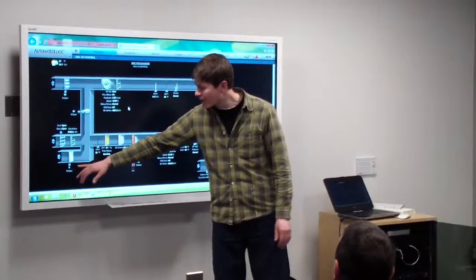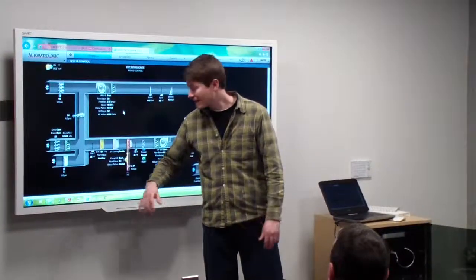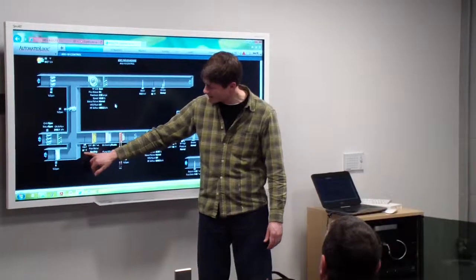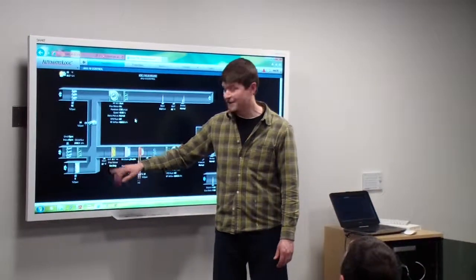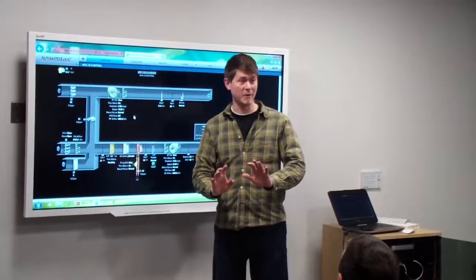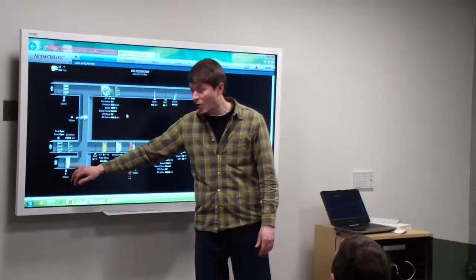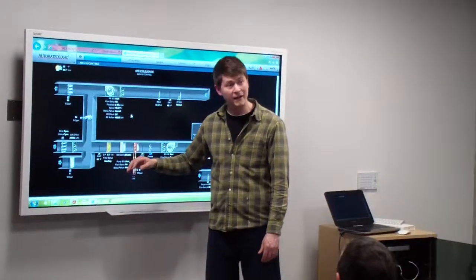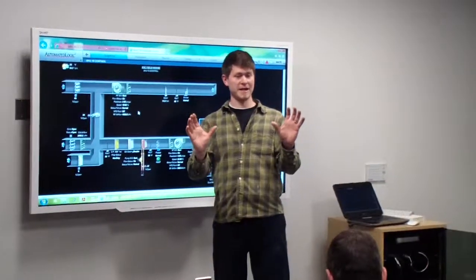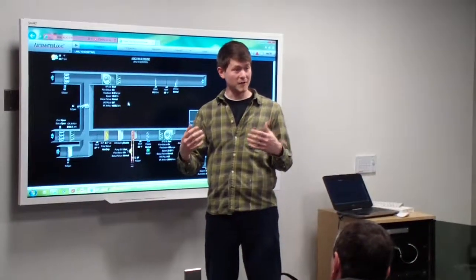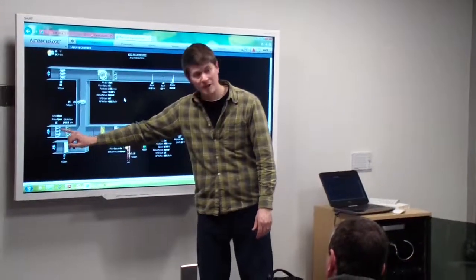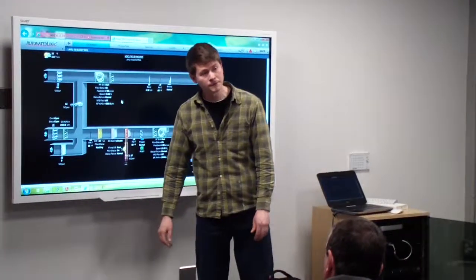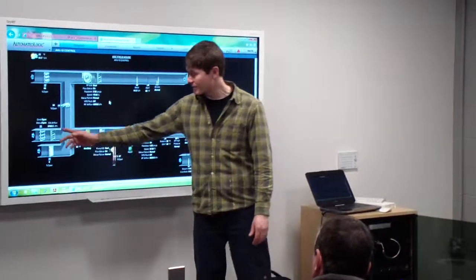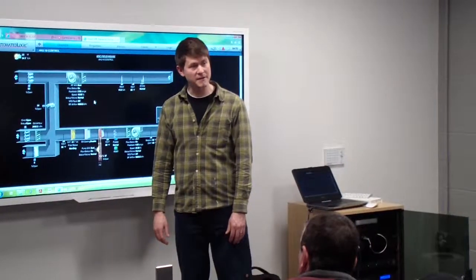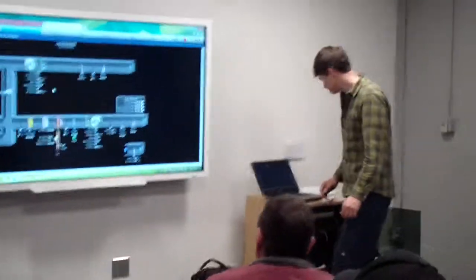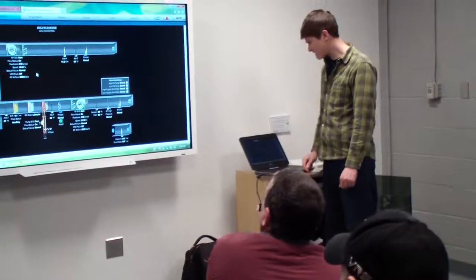Right now we have the outside air closed just because of how cold it's been. With this much outside air, we're actually seeing a 37-degree mixed air temp, and in order to protect what's going on, they close off the dampers. But as the temperature starts coming up a little bit more, this will start to open, which allows more outside air in. You actually have 3 sections coming in from the outside. 2 of those are closed off because this is the minimum requirement for outside air right now. That's 100% open, so 2,500 is really what you're bringing in from the outside. So I don't know if that answers your question.